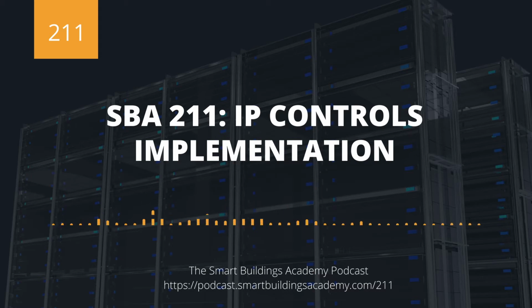And so you implement these solutions, and then you have to basically go and re-implement your solution. And a lot of people don't cost for that in projects. They don't look at what is the cost of readdressing, rediscovering, and switching all our gear over to the new IT network. Because of that, they lose about 20 to 40 hours of labor on IP controls projects. Fortunately, that's something you learn on your first IP controls project, and you usually don't end up doing that again.